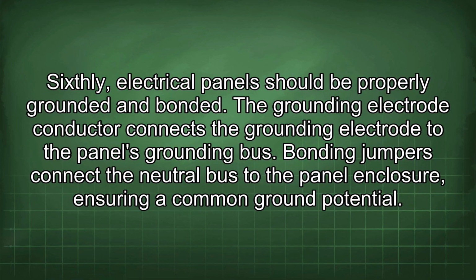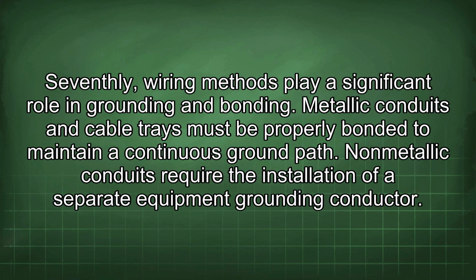Sixthly, electrical panels should be properly grounded and bonded. The grounding electrode conductor connects the grounding electrode to the panel's grounding bus. Bonding jumpers connect the neutral bus to the panel enclosure, ensuring a common ground potential. Seventhly, wiring methods play a significant role in grounding and bonding. Metallic conduits and cable trays must be properly bonded to maintain a continuous ground path.